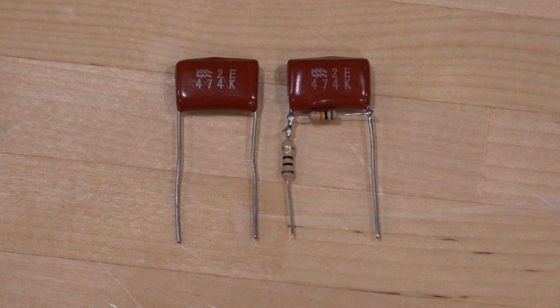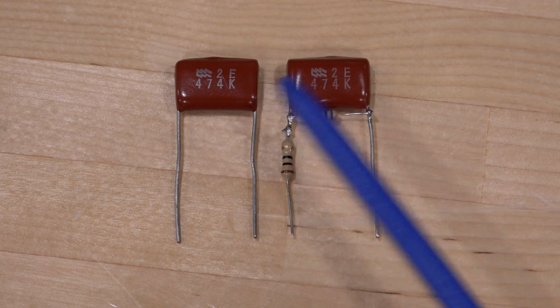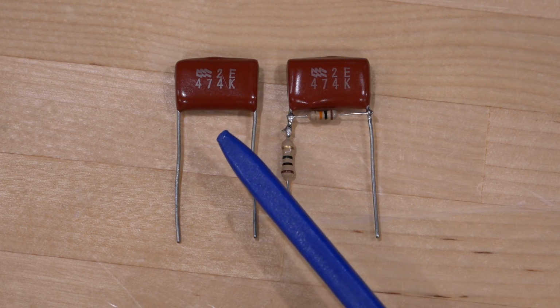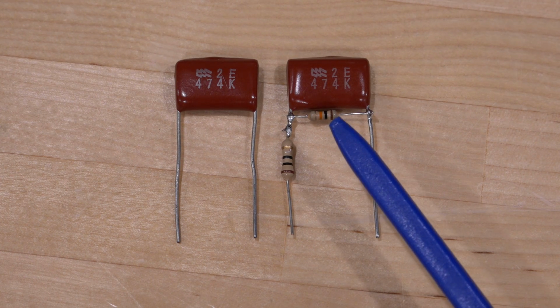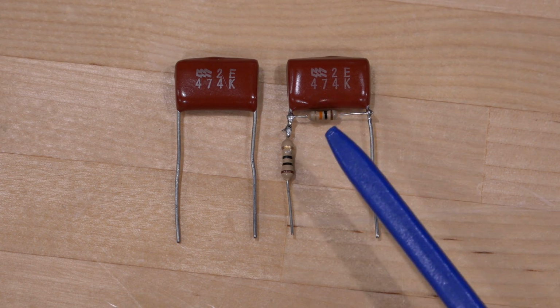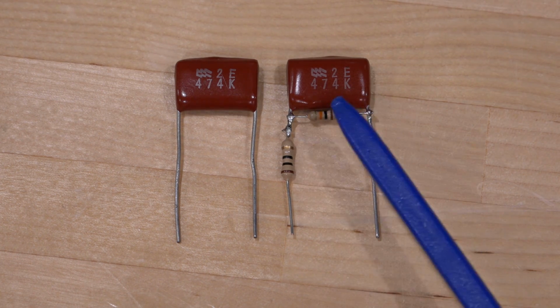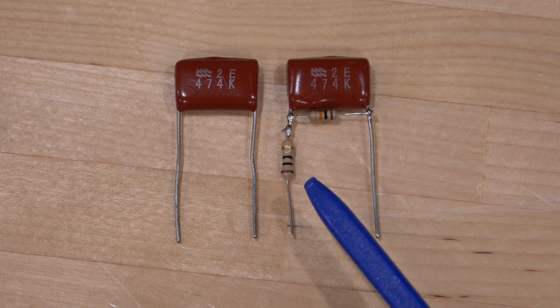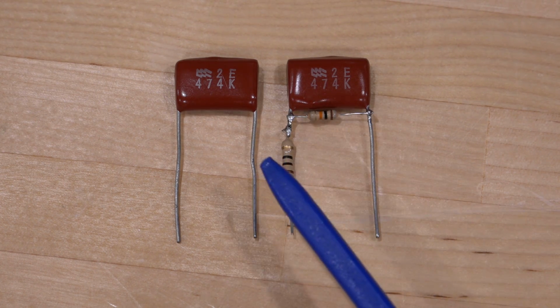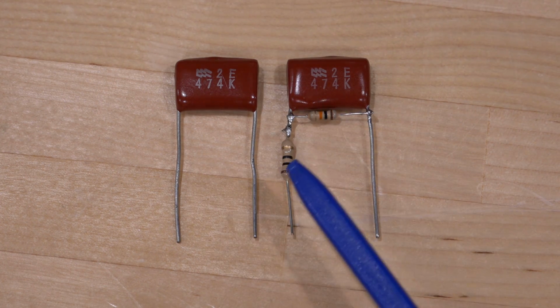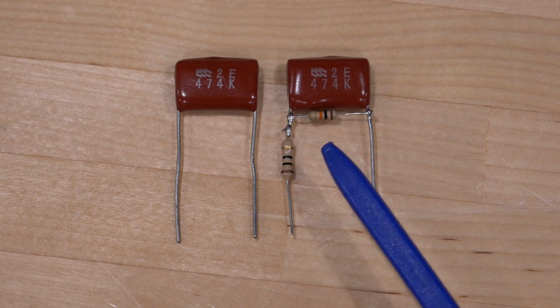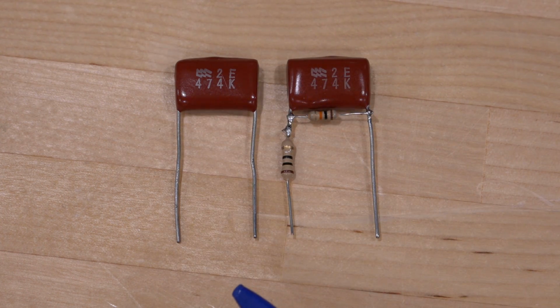Let's do a quick experiment seeing the benefit of looking at RS and RP simultaneously in this instrument. So I have two capacitors that have the same nominal value. The one on the left is original, and the other one on the right I have modified by adding some parasitic resistances to it, one in parallel at 10 kilo ohm and one in series at 10 ohm. So of course these are going to have different equivalent models, especially because there are two resistors involved, and depending on the frequency you're going to get totally different values. Let's see how the instrument reacts to this.